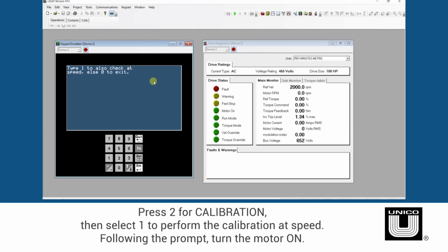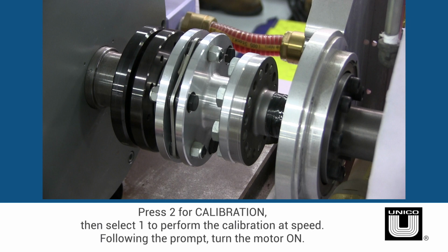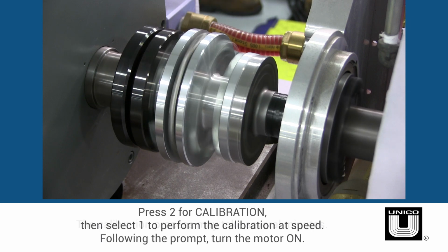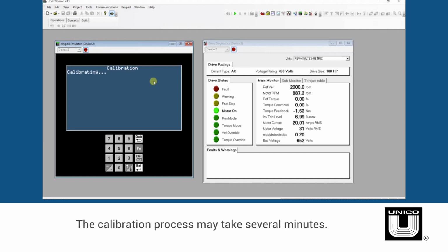Select 2 for the calibration test, then select 1 to perform the calibration at speed. Following the prompts, turn the motor on. Once the motor is on, the drive will rotate a current vector at 1/4 of the rated frequency and 1/2 of the rated current. As you can see through the drive diagnostic window, the motor velocity is at 900 RPM, which corresponds to 60 Hz, and the motor current is at 20 amps. The moving calibration is more accurate than the other calibration, so this method is preferred for the IPM startup procedure. Please note that the moving calibration may take several minutes to complete.